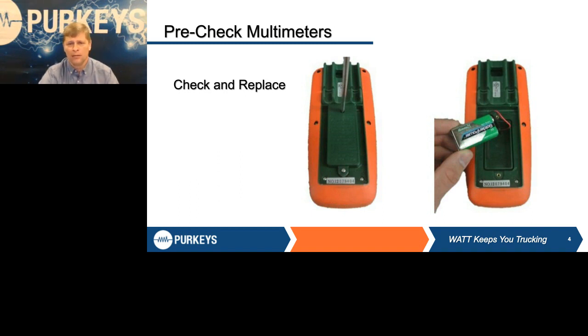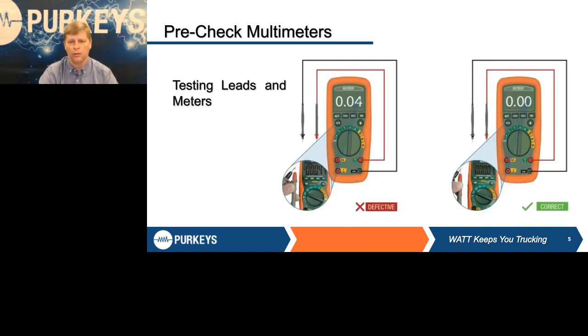So once we've done that, we want to check our leads. The easiest thing we can do is turn our meter to ohms and touch our two leads together. The meter should zero out. If it doesn't, it tells you either you've got bad leads or you've got a meter that's out of calibration. If you look at the slide here, the one on the right zeroes out, the one on the left doesn't, and it lets us know that hey, there is something wrong with that meter.